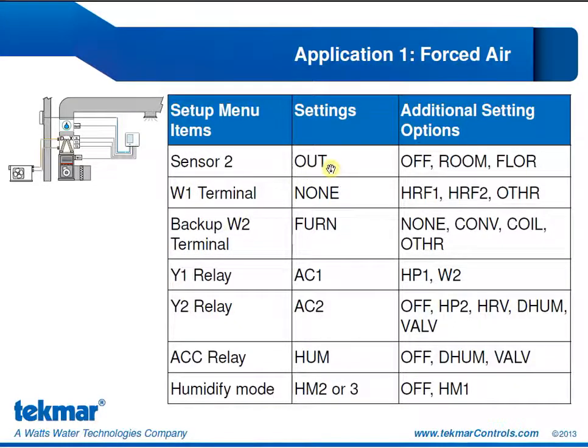Here are the essential settings for this application. Sensor 2 is being configured for the outdoor sensor. It's not going to sensor 1 because sensor 1 cannot be configured to be an outdoor sensor. W1 terminal is being set to none. The reason that's being set to none, let's look at the setting options. Our only options are for a high mass radiant floor or a low mass radiant floor, or other. So we're not going to control the furnace through the W1 terminal. We're going to control it through the W2 terminal, which we can configure to operate a furnace.